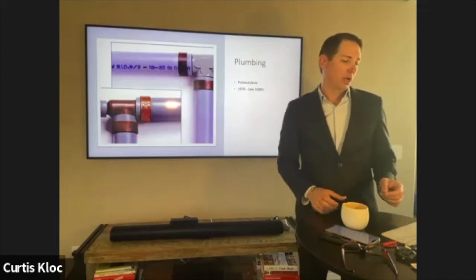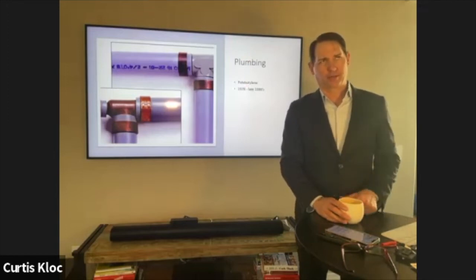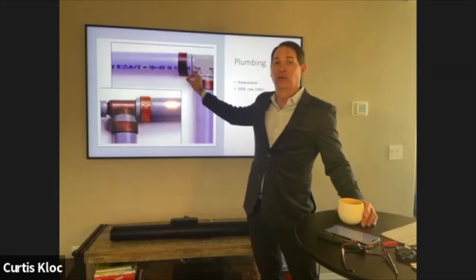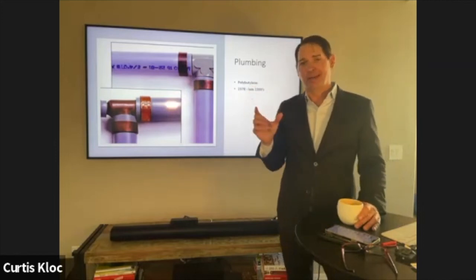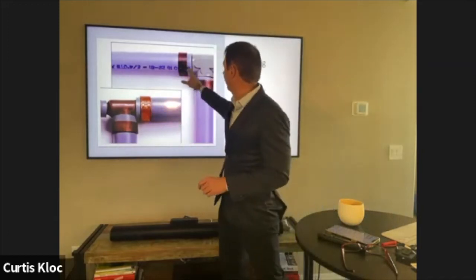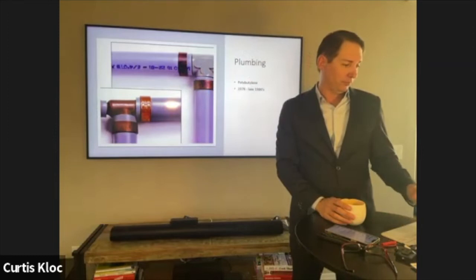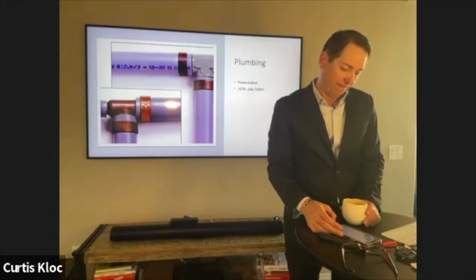Listing agents sometimes argue that piping isn't polybutylene, but there's a PB number and an ASTM number printed right on the piping — just Google it. If it doesn't come up as polybutylene right away, there's more than one ASTM number: one for the fitting, one for the T-joint, and one for the piping itself. After three tries you'll definitely find the ASTM numbers to confirm it.